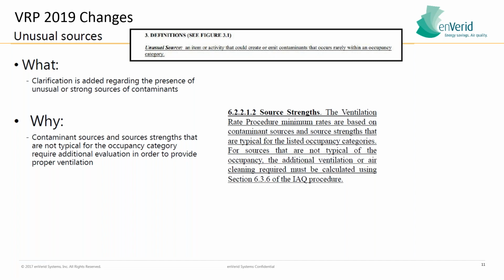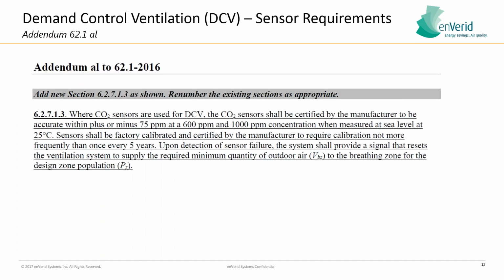So for example, if you're building a school next to an airport where outside air might be contaminated, the intent of the ventilation rate procedure is not to bring all that contaminated outside air into that school. The intent, as referenced here in 6.2.2.1.2 under source strengths, would be to use the indoor air quality procedure and air cleaning to be more in line with outside air reductions for ventilation in 2019. Very interesting, and good to have that clarity from ASHRAE as well.